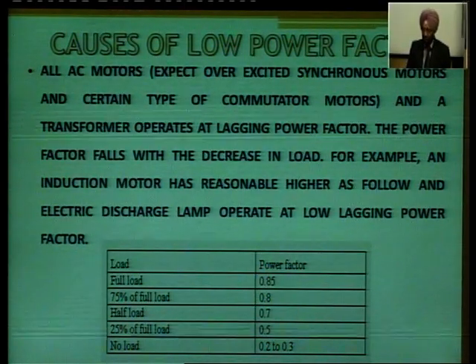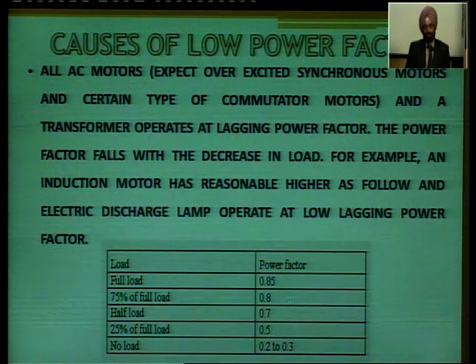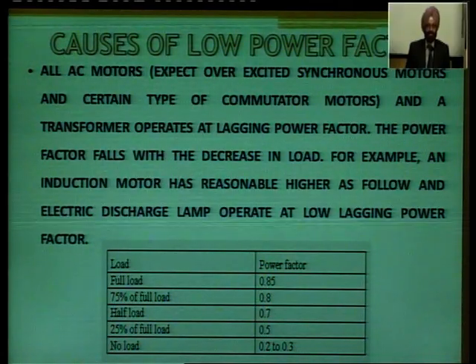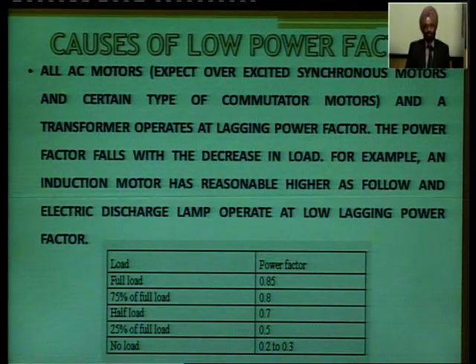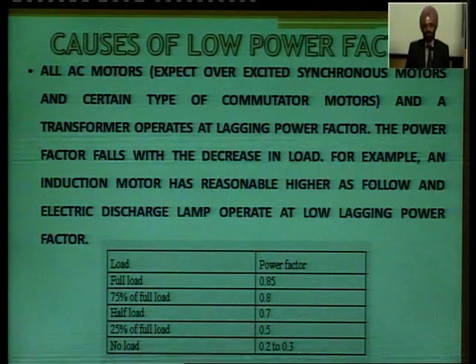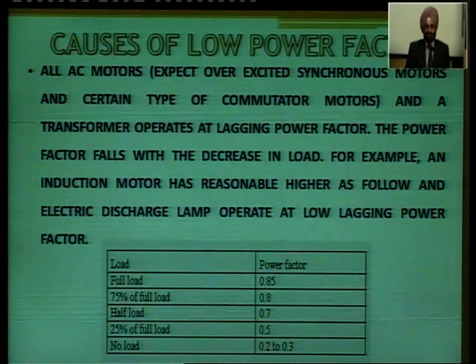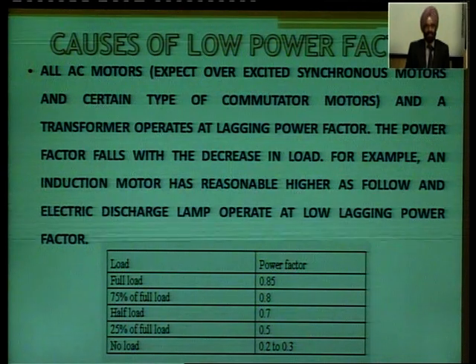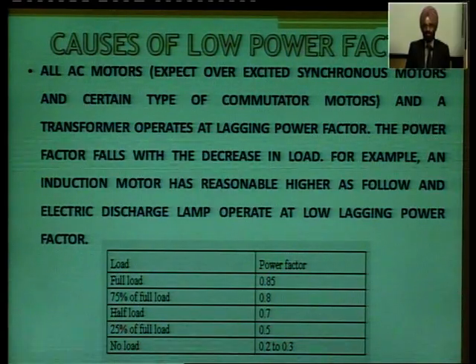Now we have to study the causes of low power factor. Students, until we know what things make the power factor fall, this is one of the most important things to be remembered: which things are the causes of a lower power factor. First of all, AC motors except the overexcited synchronous motor, which we will study later, and a transformer operated at lagging power factor: the power factor falls with decrease in load. For example, an induction motor has a reasonably higher power factor at full load, whereas an electric discharge lamp operates at a lower lagging power factor.